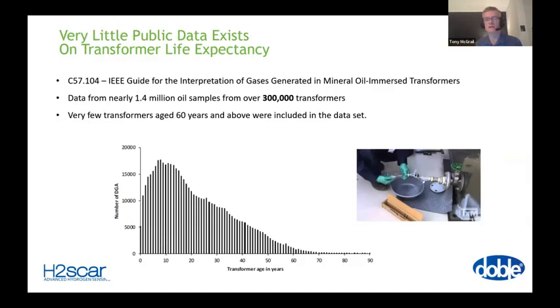But the question is, why are there fewer transformers which are older? Some will have been removed from service, some will have failed in service, some will have been exchanged for larger transformers due to load reasons, etc. So we need to know why. And this graph doesn't tell us that. It just says there are more samples from younger transformers than older. Okay. Need a bit more to it to get that information.